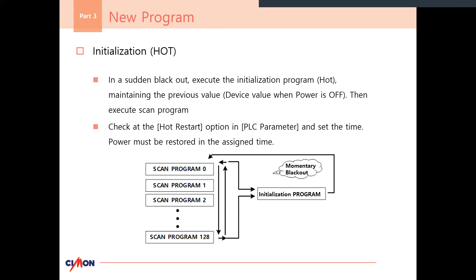If you happen to not predict the blackout properly, you will lose all that data, because internally it is waiting until that time limit to actually send the data back into the scan program. So it's a bit of a double-edged sword. It's keeping your volatile memory handy, but only for as long as you declare. It can't detect when the power comes back to your plant. You would have to tell it the power is going to come back in like 60 seconds, a minute.